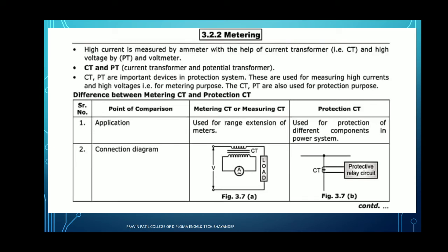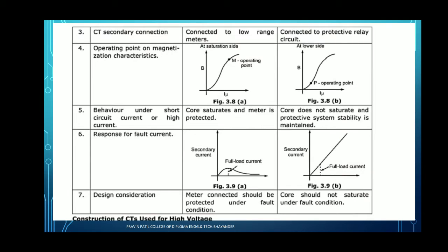Next, we have to see the connection diagram representation. Here, the CTs are connected towards the load, and the protective CT is directly fed to the protective relays. One terminal of that current transformer is connected to the overhead line, and the other terminal is directly connected to the protective device, a relay. So this is the connection diagram for the protection CT, and the other is the connection diagram for the metering CT or measuring CT. The CT secondary is connected to a low range meter for metering purposes, as also for the CT protection.